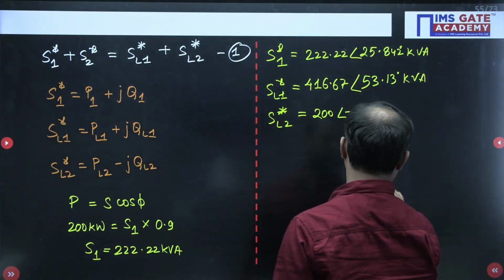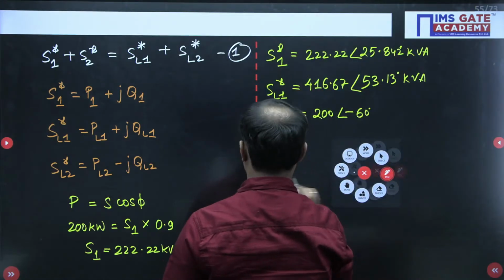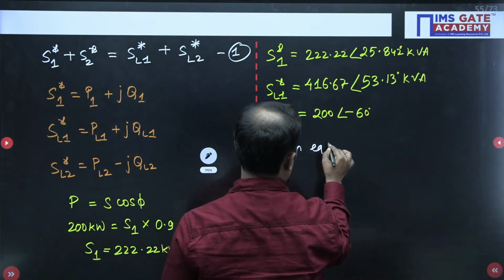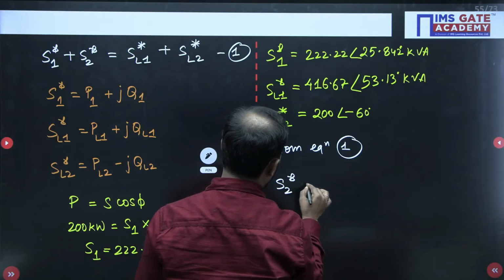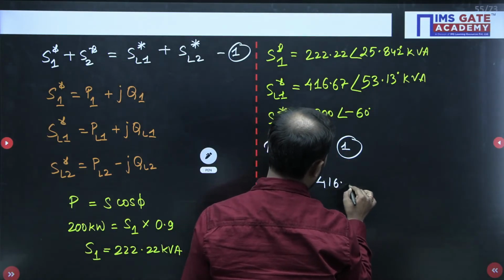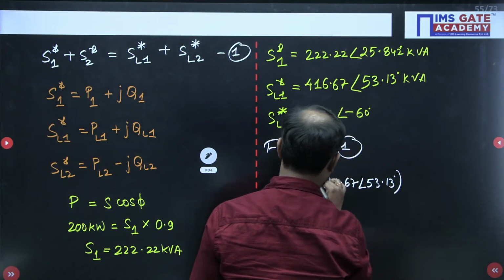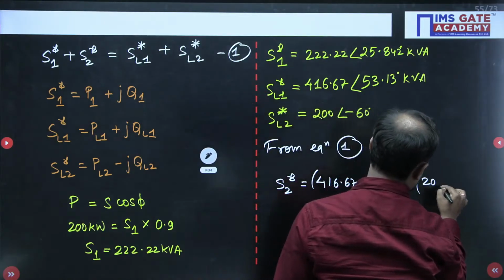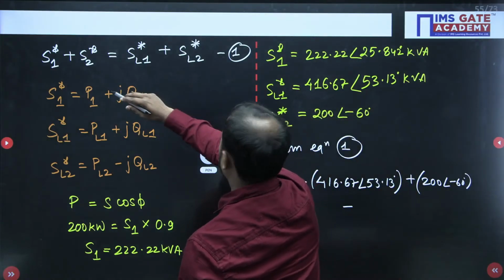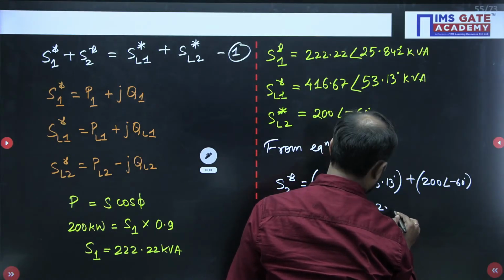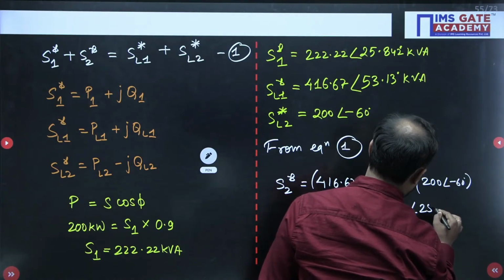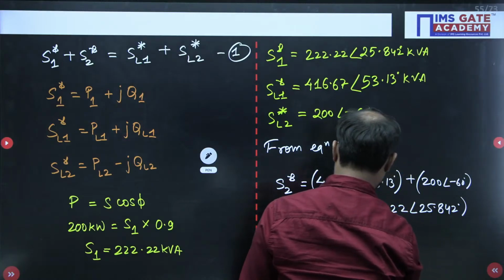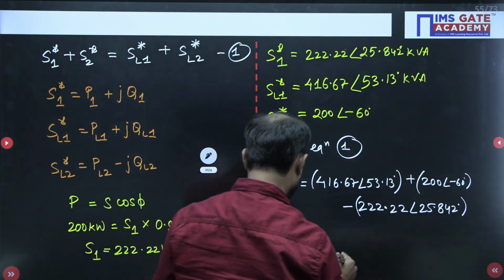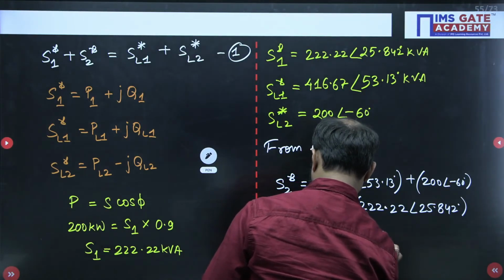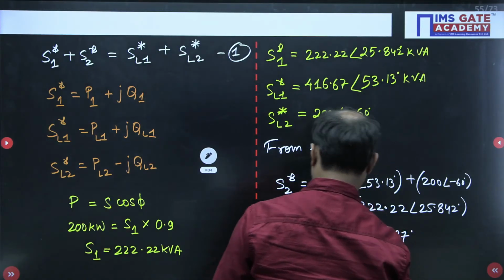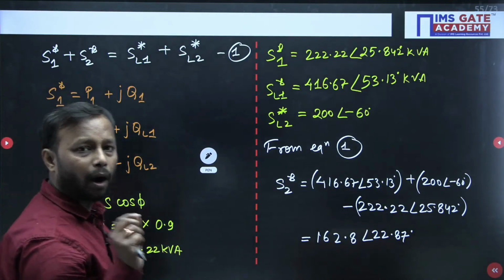Now from equation 1, S2 conjugate equals SL1 at 416.67 angle 53.13 degrees plus SL2 at 200 angle minus 60 degrees, minus S1 conjugate at 222.22 angle 25.842 degrees. This value comes out to be 162.8 at angle 22.87 degrees. This is S2 conjugate, but we need to calculate the power factor and its nature, whether leading or lagging.